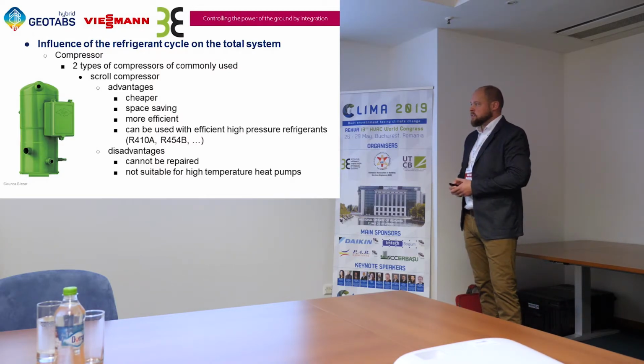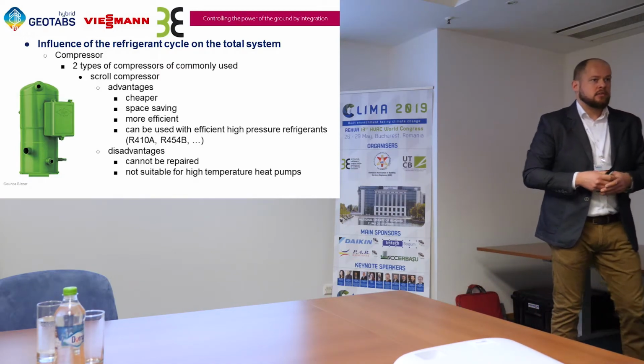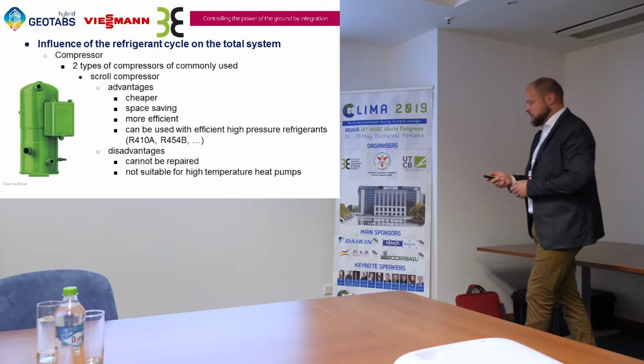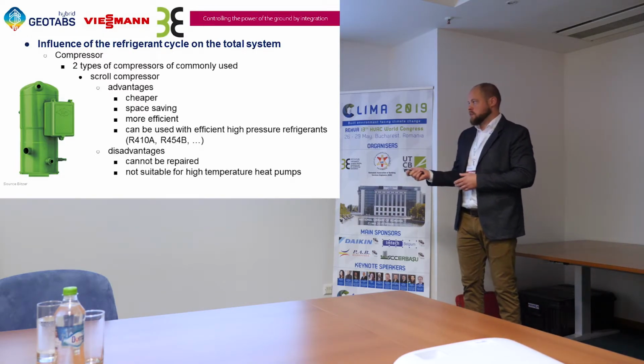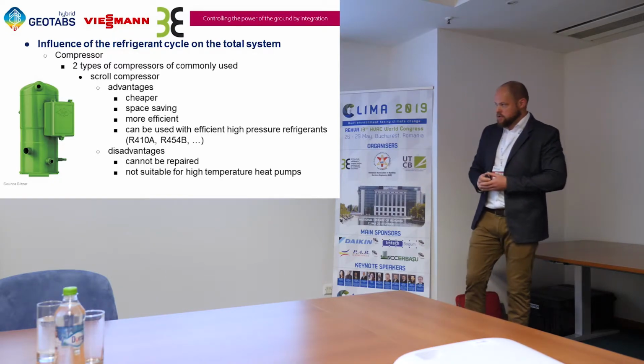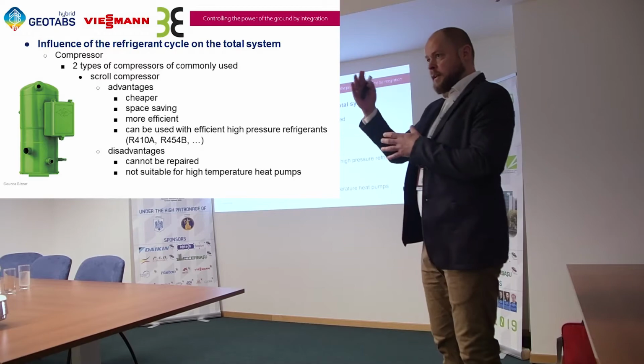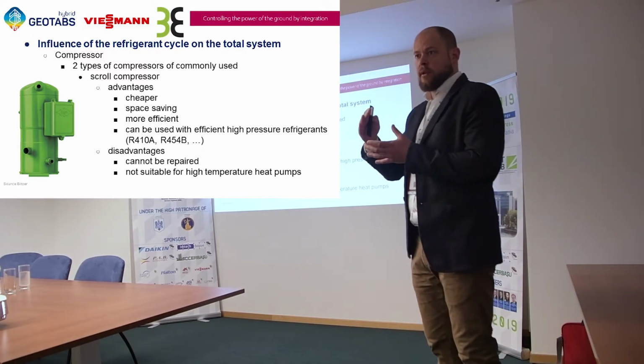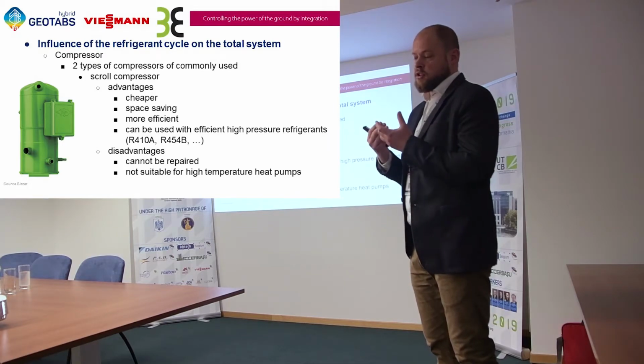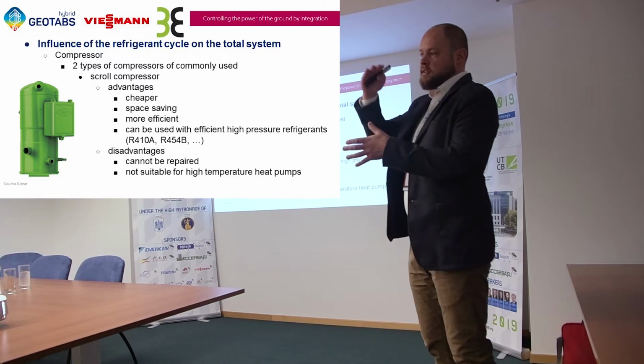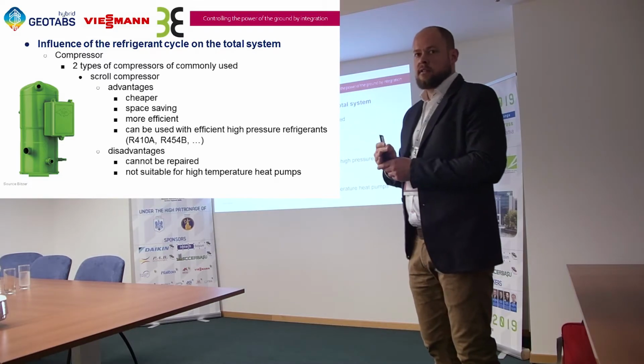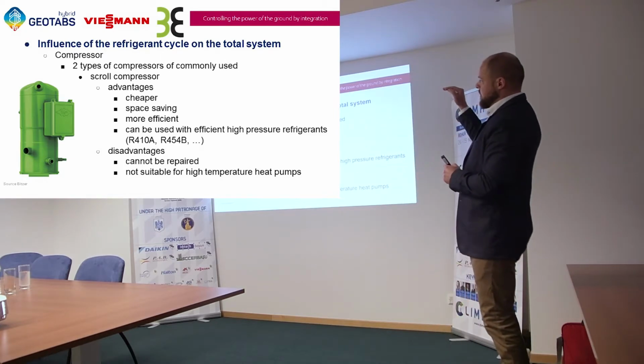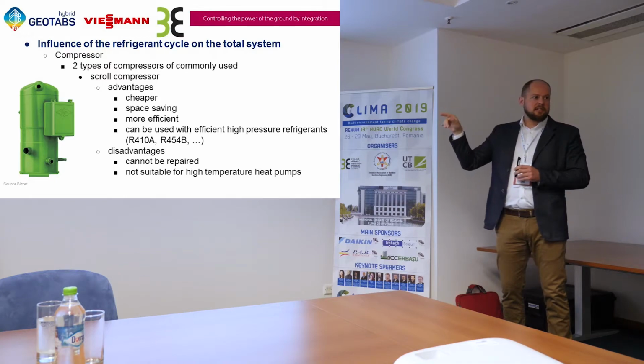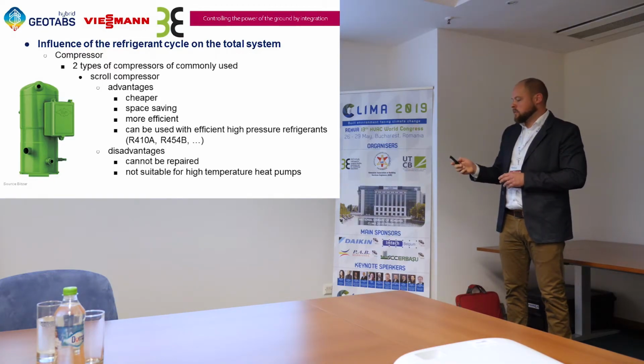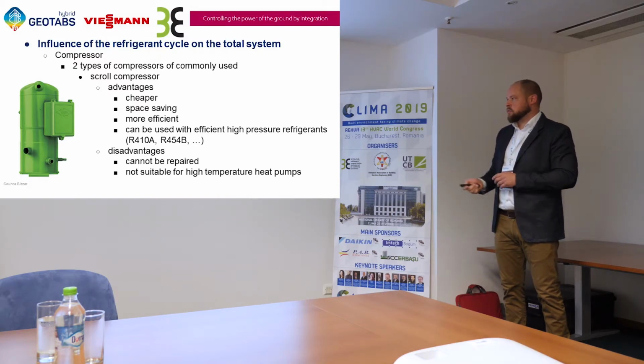The disadvantage of this system is that it cannot be repaired. So when we break the compressor due to liquid inside the compressor, we have to change the entire compressor, or when the electrical motor gets burned, we have to replace the total system. It's also not suitable for high temperature heat pumps because they work with a fixed delta P. So the pressure difference over this type of compressor is fixed. It's depending on the suction pressure from the evaporator, and then it's a fixed increase of pressure to the condenser side. That's also negative sometimes when the condensing temperature is a bit higher, that we have an under compression in this type of compressor. That's something that can happen with this type of compressor. That's not so very bad.